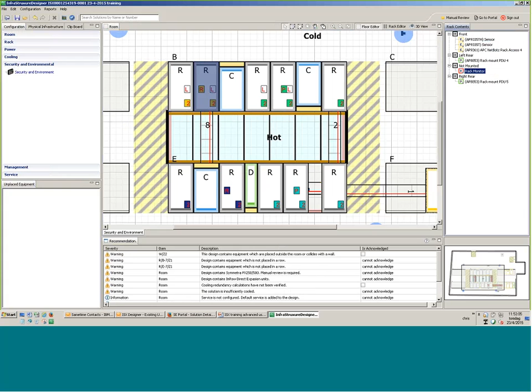So if I zoom a bit closer here, now I see in my racks, I have rack access and my 2 sensors. In this rack, I have rack access, 2 sensors, and, which is not mounted here, a rack monitor, which is then my NetBotz device.